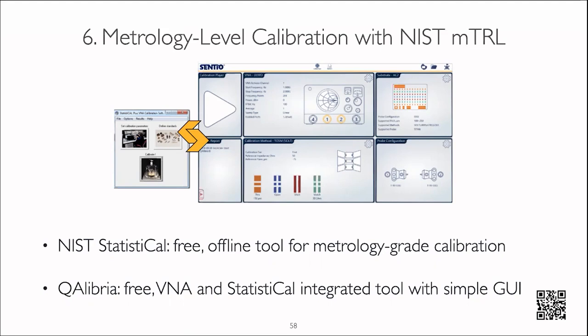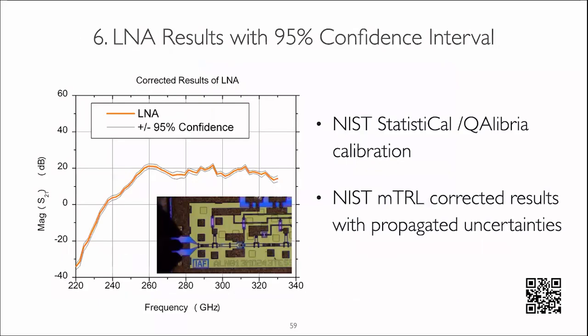We suggest using QAlibria calibration software, which is also free of charge and freely downloadable from the MPI web page. It connects this statistical calibration engine with the graphical user interface of QAlibria, and makes the very complicated calibration routine very easy to use and implement in daily calibration practice. And last but not least, this is an online calibration, which means that QAlibria measures the S-parameters of the calibration standards, and once the error terms are calculated by the statistical engine, QAlibria sends them back to the network analyzer. So you can calibrate the entire setup for your live measurements, operating just one software graphical user interface.